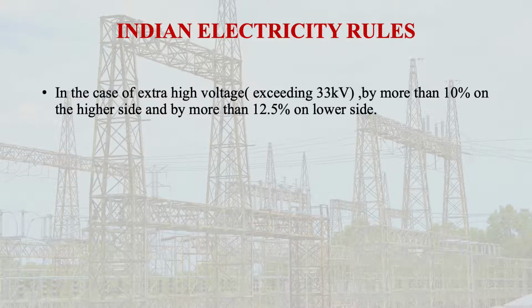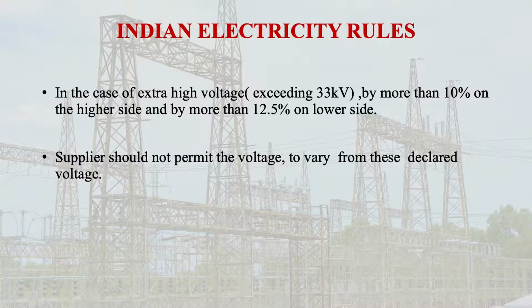Now in case of extra high voltage, meaning voltage exceeding 33 kV, the limits are more than 10% on the higher side and more than 12.5% on the lower side. That means it should not vary more than 10% on the higher side, and not more than minus 12.5% on the lower side. For example, suppose extra high voltage 132 kV. The supplier should not permit the voltage to vary from the declared voltage by more than 10% on the higher side. That means only plus 10% is allowed. And on the lower side, it can decrease only within 12.5%.